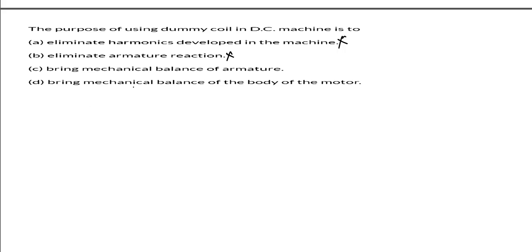Bring mechanical balance of the armature, or bring mechanical balance of the body of the motor. So these are the two options you have. So what will be the possibility here? First of all, when we use a dummy coil, is it in lap winding or wave winding? I am giving you the task to find where the dummy coil is used, whether in lap winding or wave winding, and what the purpose of the dummy coil is. Please provide your answer in the comment box. I am giving the answer: to provide mechanical balance of the armature.